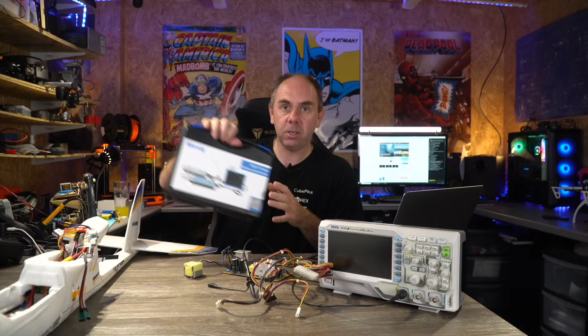And C, more than anything, you'll fry the lead and give yourself a pretty nasty surprise. This is where a differential probe comes in. What it does is isolate your inputs from the mains reference earth, by putting lots of resistors inside between your device and the scope, and it has a built-in amplifier. So it weakens the signal then boosts it again, but separates it off, with optocouplers and things like that involved.